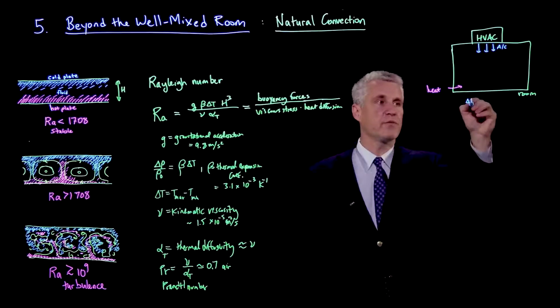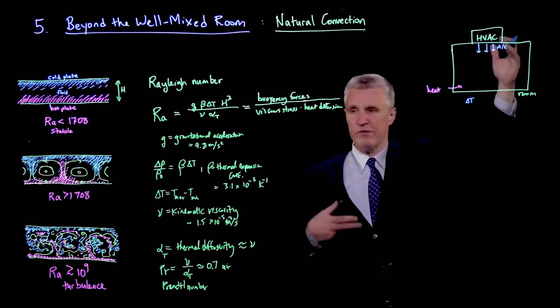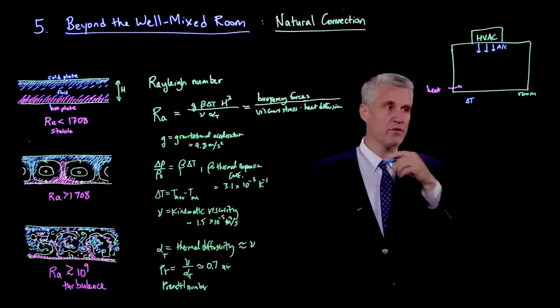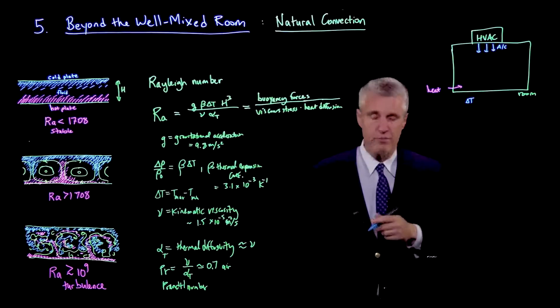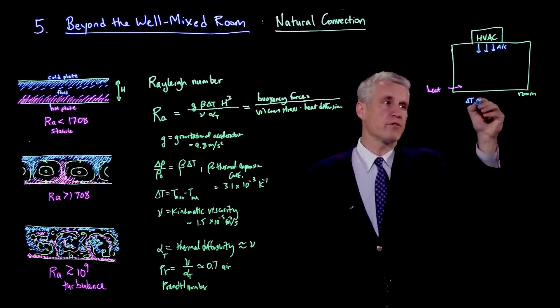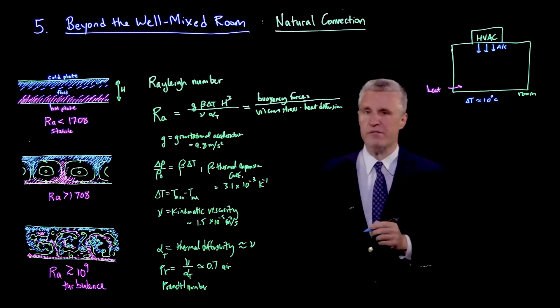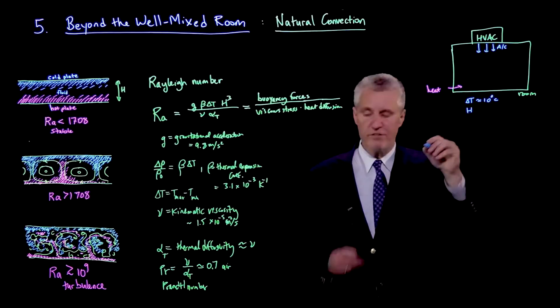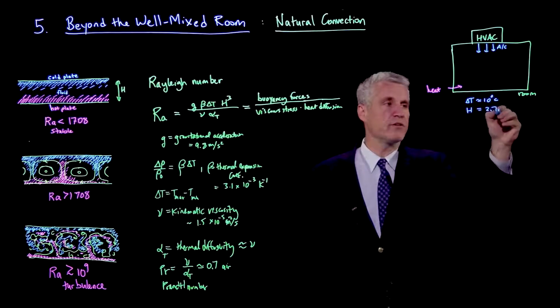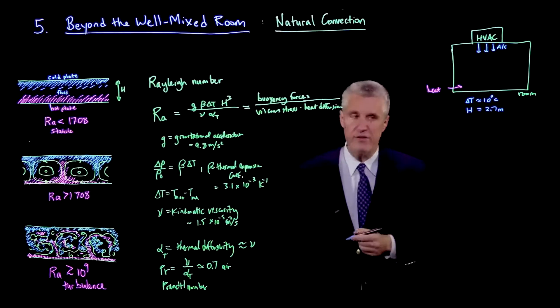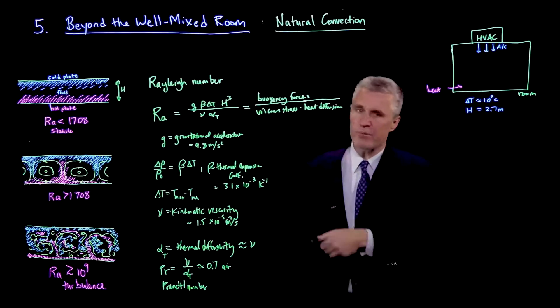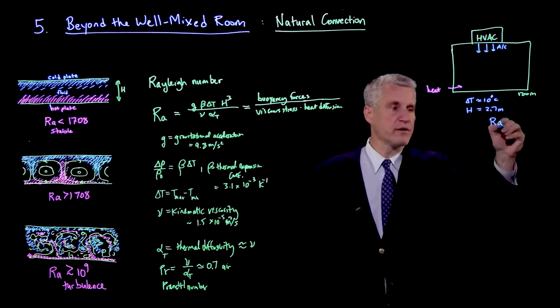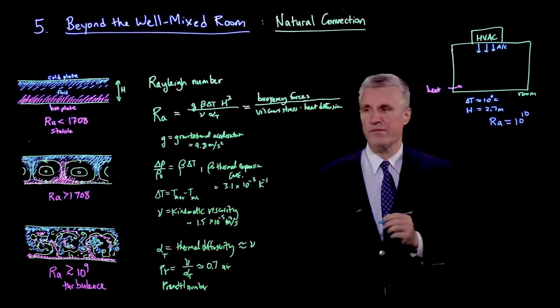Let's actually put some numbers in here. What if we say that the temperature difference between the fluid we're injecting, whether it's heating or cooling, relative to the background air in the room, which is closer to the target temperature, is only 10 degrees C? That seems like not a very big difference. But then we go back to our height, which is our length scale, and we say it's 2.7 meters, just as a standard ceiling height. If you plug in the properties of air with these numbers, the Rayleigh number is actually 10 to the 10. It's enormous.